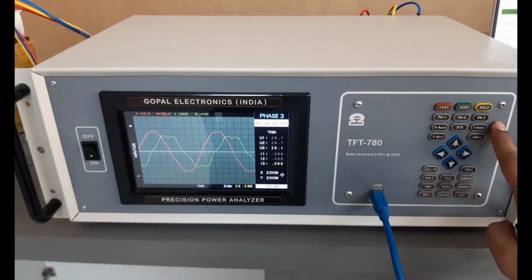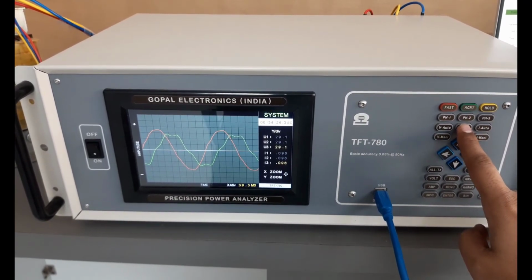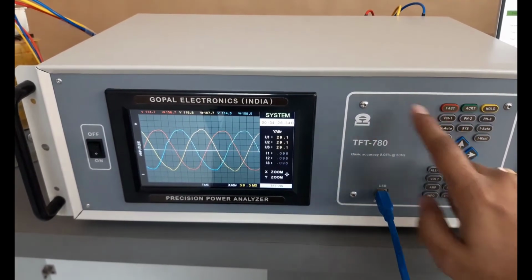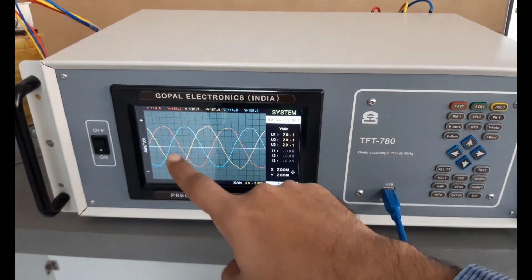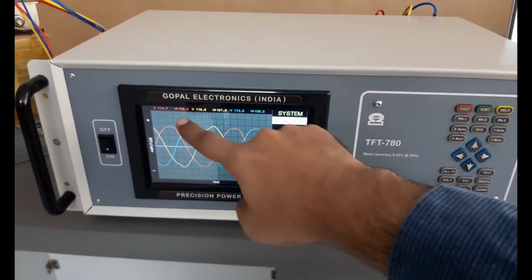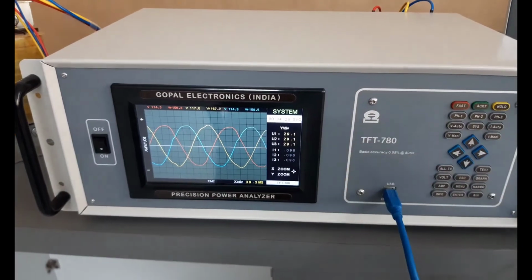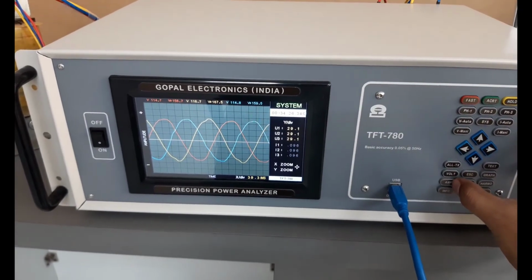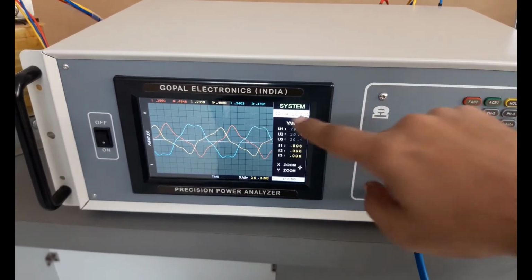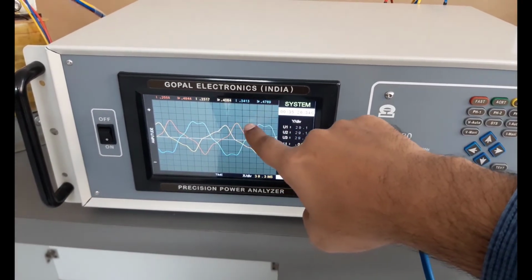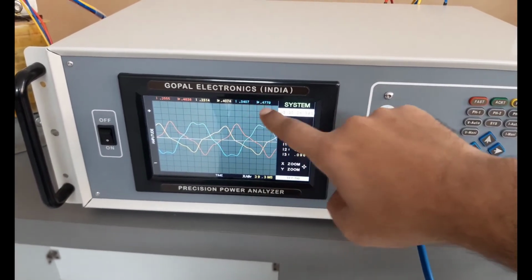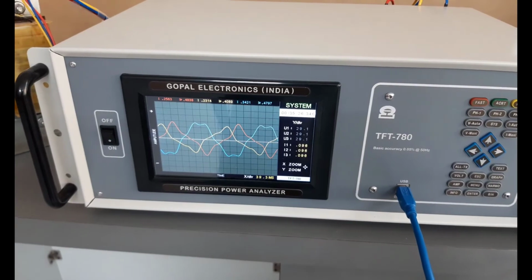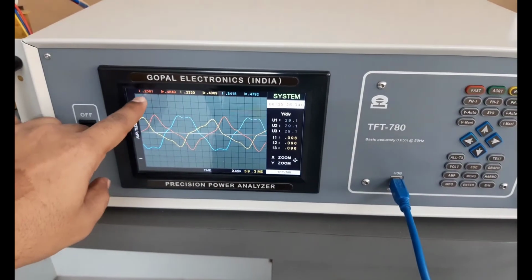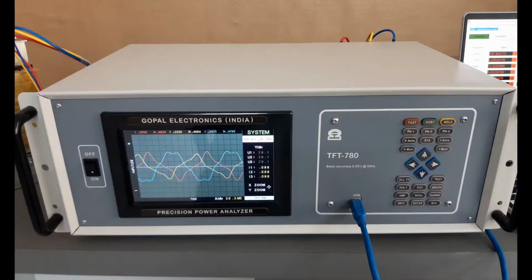And if you want to see system waveform, then you can press system, it will display all voltage waveform R, Y and B and its magnitude on the top of the display. If I press ampere key, it will display system ampere waveforms for I, R, Y and B. This is RMS ampere and this is peak ampere.